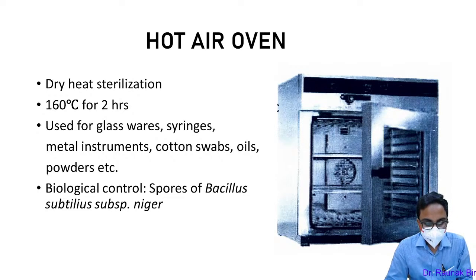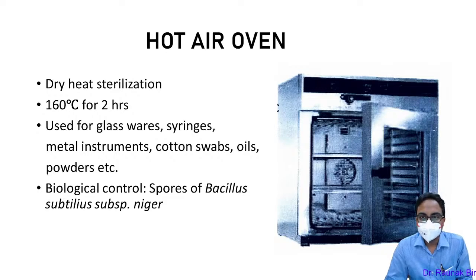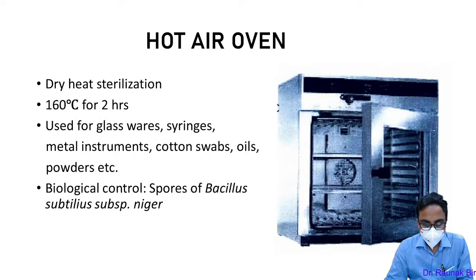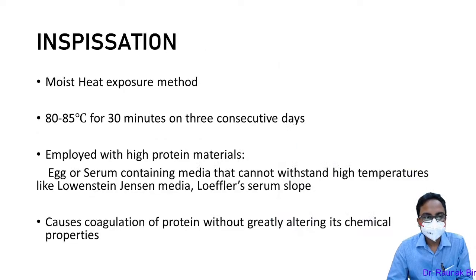For every method, we have a biological control indicator. If it comes negative, the process is running well. Here we use spores of Bacillus subtilis subspecies niger. If the spore grows and you have visible growth after the process, it means the spores are not killed and the process has failed. If you get a sterile culture plate after the process from the spores, the biological control was satisfactory.